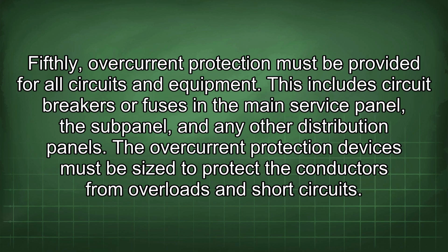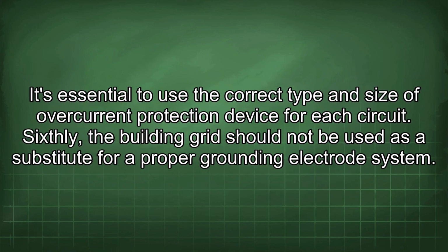Fifthly, overcurrent protection must be provided for all circuits and equipment. This includes circuit breakers or fuses in the main service panel, the subpanel, and any other distribution panels. The overcurrent protection devices must be sized to protect the conductors from overloads and short circuits. It's essential to use the correct type and size of overcurrent protection device for each circuit.